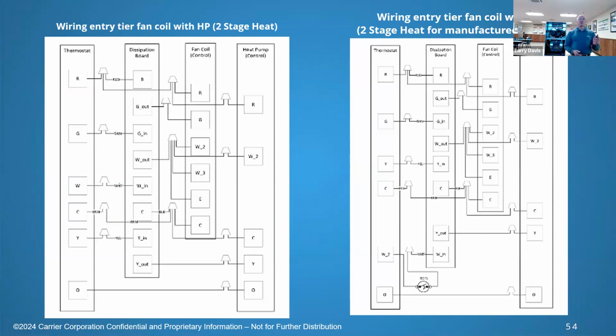On all of them, you see the G out and the G in, everything goes through that dissipation board. It has some level of priority. The thermostat can tell it to call, but that dissipation board is what allows things to run. And we also want that G output to the dissipation board to be able to energize that fan in the event of a dissipation. Okay.